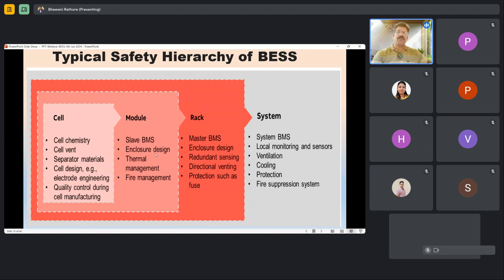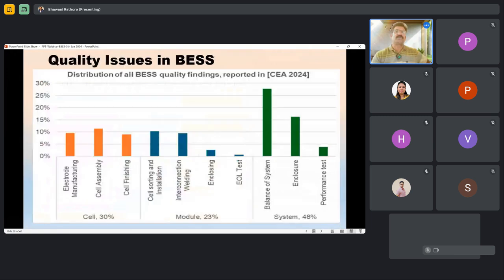How the thermal management and fire suppression work - in case of fire, how we manage it. Overall, the complete master BMS, enclosure design, redundant sensing - directional sensors should be redundant, so if one fails, another should work. Directional venting, protection such as fuses. Overall the system works with battery management system, local monitoring and sensors, ventilation, cooling, protection, fire suppression. Only when all these things are okay can we ensure the safety of BESS.